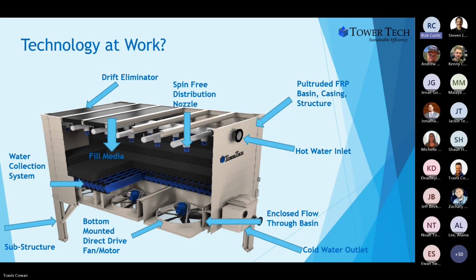So then as the water goes through the fill material, it hits another component that we developed, and that is a water collection system. At this point, the water is flowing out of the fill media into these channels. Those channels are collecting the water and distributing it to the perimeter of the cooling tower, which now becomes your basin. However, air is being pushed up through the cooling tower, and it can flow through the water collector and hit the fill material, go up past the water distribution system through the drift eliminator out top. So we're an upflow design, but we can collect all the water into this perimeter basin.